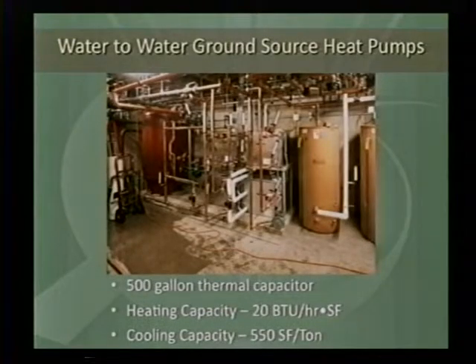And so what we did was we added a 500-gallon tank as a kind of thermal capacitor. And that tank is a hot water tank in the winter. This is all before the insulation went on all the systems. And it's a chilled water tank in the summer. We run it in the winter from 105 to 115. The temperature that we're running it at is primarily what we need at the heating coil in the air handling unit. We have a mixing valve on the return loop on the floor slab to basically drop it down to the 75 to 80 degree temperature we try to run the floor slabs at.